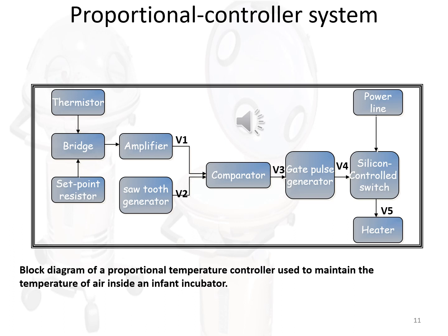Temperature-controlled air is passed through the chamber in which the baby is located to maintain it at a set temperature. The temperature in the air supply line varies a thermistor resistance that is compared with a fixed resistance that corresponds to the set temperature. If the temperature of the air entering the infant's chamber is lower than the set temperature, power is applied to the heater to correct for this difference.